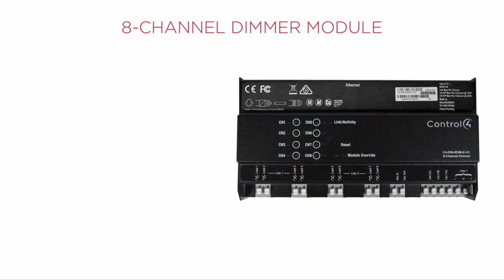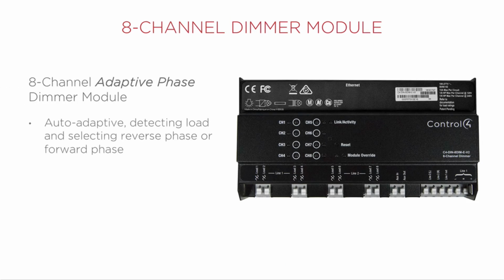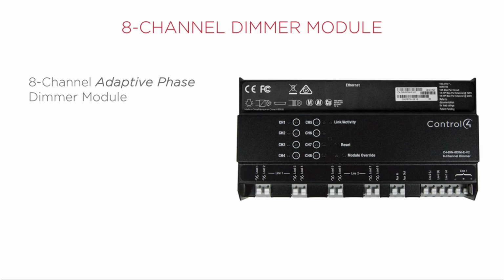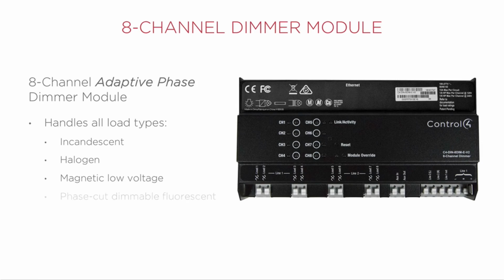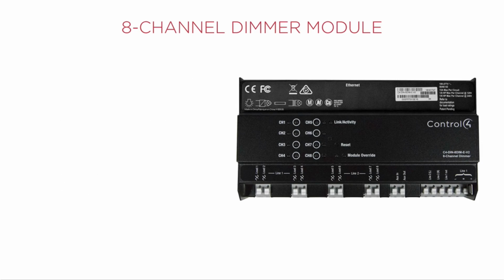The 8-channel dimmer module comes in 2 different models. The adaptive phase dimmer module is auto-adaptive, detecting the load and selecting reverse or forward phase automatically. Reverse or forward phase can also be set manually if needed. The adaptive phase dimmer module can handle all load types: incandescent, halogen, magnetic low voltage, phase-cut dimmable fluorescents, phase-cut dimmable CFLs, and phase-cut dimmable LEDs.